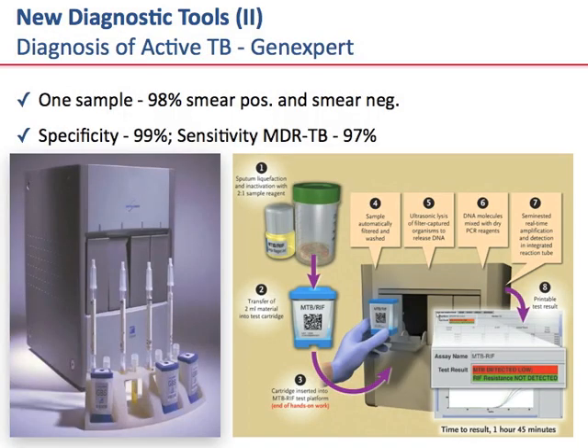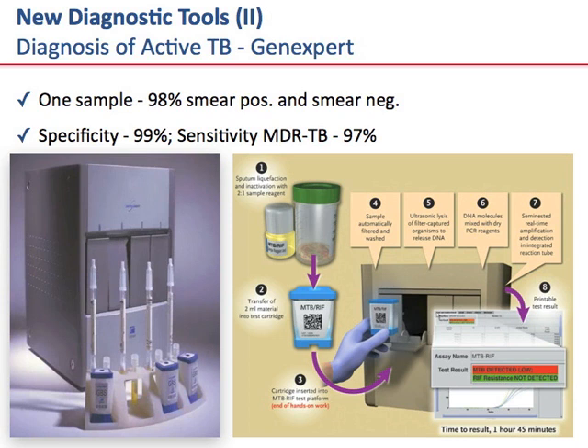What has been transformative is the widespread use of the GeneXpert. This is a device produced by Cepheid in which sputum is mixed two to one with a liquefying reagent, and the cartridge is placed in essentially a robot. Within two hours it provides the diagnosis of TB and also whether there is rifampin susceptibility or resistance. One sample identifies 98% of the smear positive and 73% of the smear negative cases. Specificity is almost 100%, in part because the gene being amplified, rpoB, is relatively restricted to M. tuberculosis. Sensitivity for the diagnosis of MDR-TB is excellent as well.